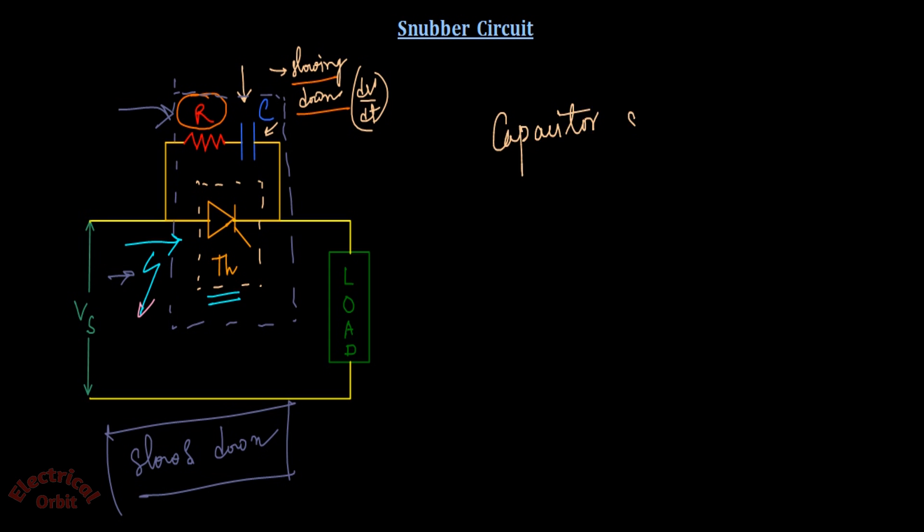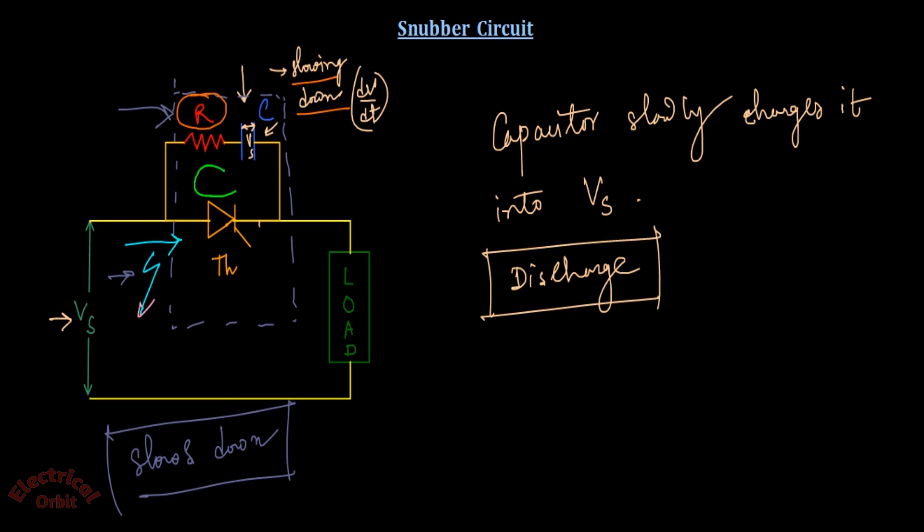See, whenever the overvoltage appears or voltage surge appears, then the capacitor slowly charges to the voltage vs. This is vs. When the capacitor is fully charged to the value of vs, then after charging it will start to discharge. Now what is the path of this discharging? It will be through this path because this is positive terminal and this is negative.